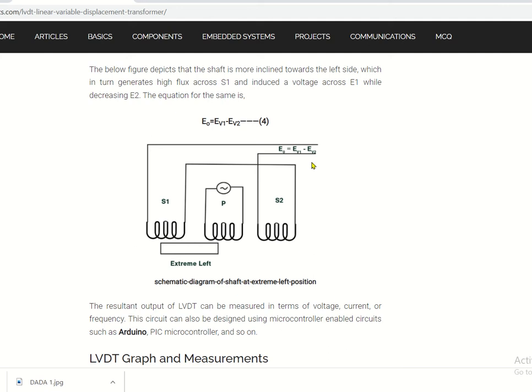Suppose we have to determine the displacement of any particular object. What we need to do is couple it to the core so that it can smoothly displace the core, and the core will get displaced along with the body. If such is the situation, then you can find that the movement of the object will ultimately result in different values of voltage across these secondary windings S1 and S2, and that is what we have to measure.